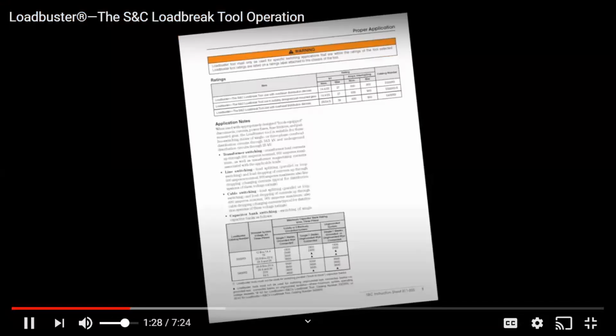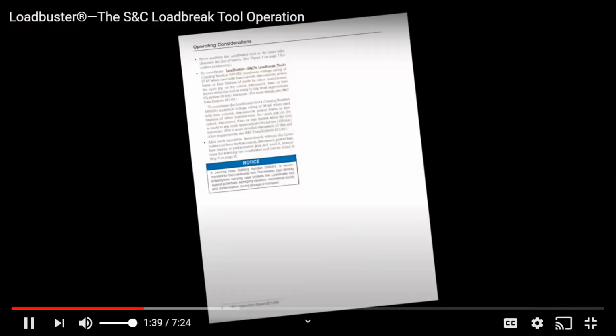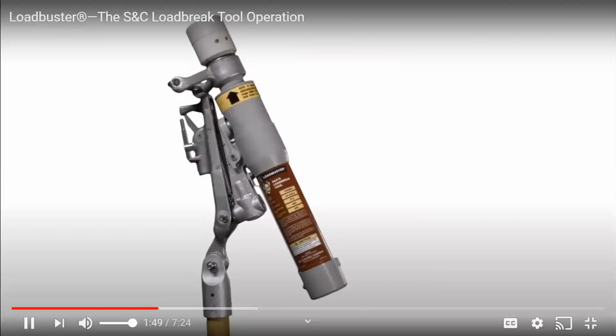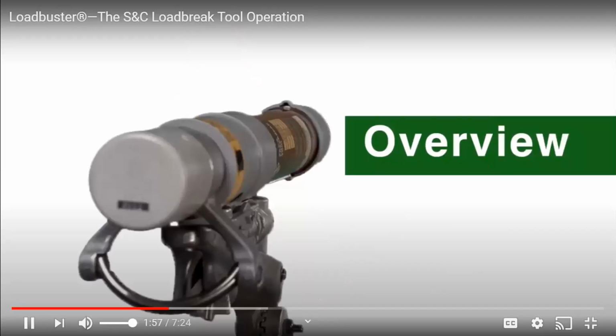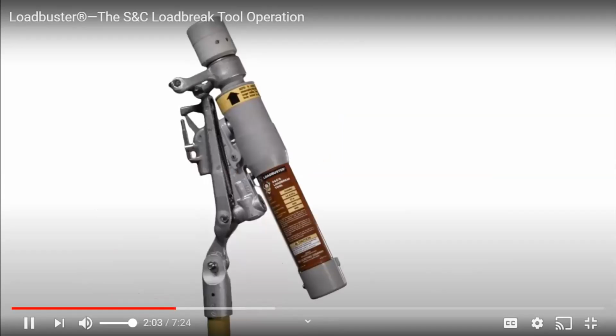Prior to using the Loadbuster tool, be sure you have read and you understand the application notes and operating considerations sections of the written instructions, because certain application restrictions apply, especially with regard to single pole switching of ungrounded primary 3-phase transformers or banks of single-phase transformers. Loadbuster, the S&C load break tool, is the original lightweight, easy-to-use, portable load break tool. It brings load switching capability through 34.5 kV and 600 amperes nominal, 900 amperes maximum to your overhead distribution system.